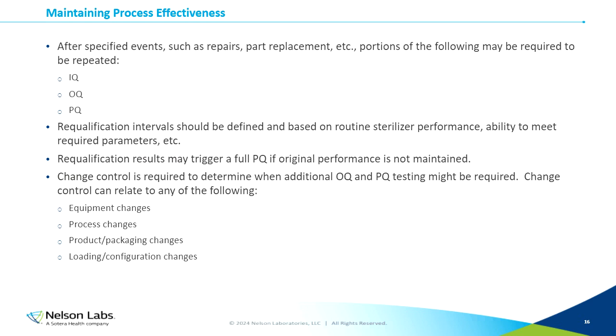Finally, once we've validated the process and we know how we're monitoring it routinely, we need to ensure that the process remains effective over time. So we need to maintain process effectiveness. After specified events such as repairs, part replacements, et cetera, portions of the following items might need to be repeated. We might need to repeat the installation qualification, the operational qualification, and/or the performance qualification.